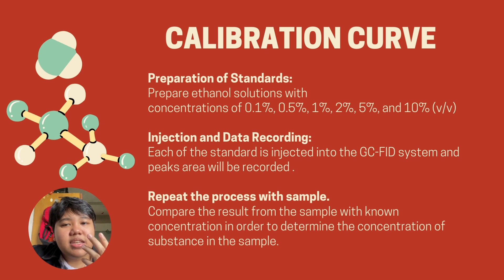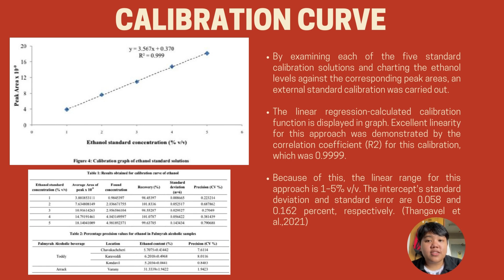So, moving on with the calibration curve, this is an example of a calibration curve that we got. This is the alcoholic beverage analysis on palm wine from Sri Lanka. By examining each of the 5 standard calibration solutions and charting the ethanol level against the corresponding peak area, an external standard calibration was carried out. The linear regression calibration function is displayed in the graph. Excellent linearity for this approach was demonstrated by the correlation coefficient for this calibration, which was 0.999. Because of this, the linear range for this approach is 1 to 5%. The intercept standard deviation and standard error are 0.058 and 0.162% respectively.